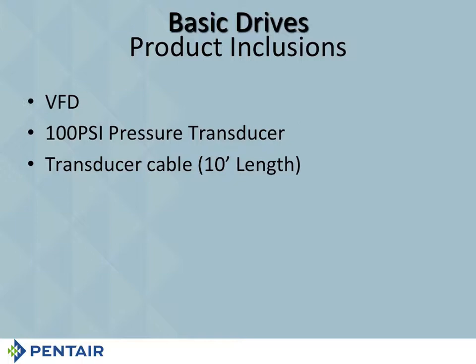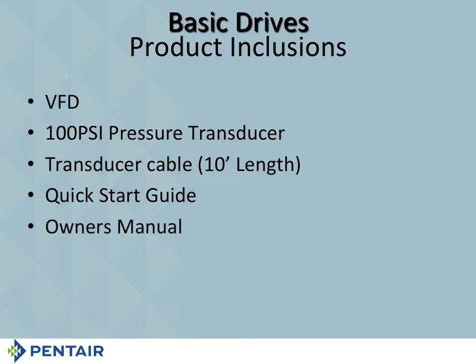Remember, your output on this transducer is only 4 to 20 milliamp, and that's a very little bit. So if it's not done correctly, if you're not splicing it exactly correct, you're going to have a problem. So we just recommend you don't splice at all. We're going to give you a quick start guide. It will help you set this drive up. Remember, it is plug and play, so it's really simple to get it started. We'll show you that. There'll be an owner's manual just in case you need it for anything.